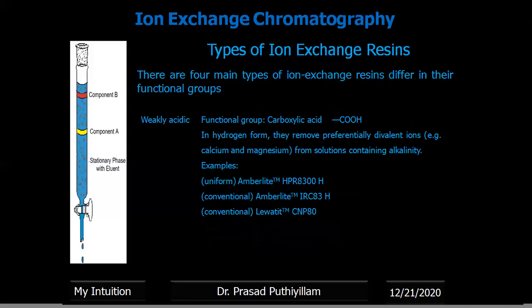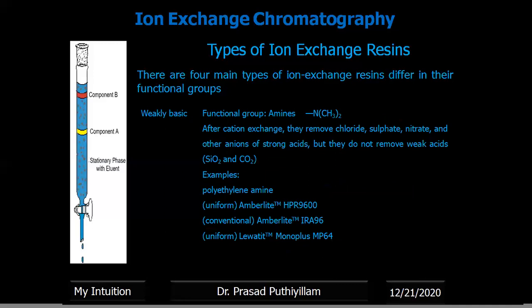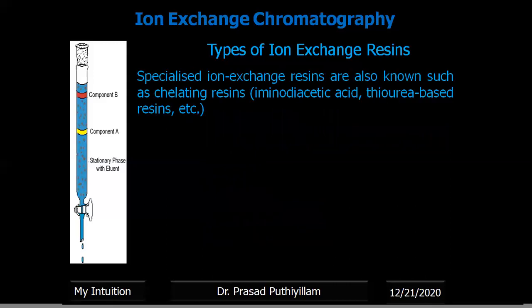Weakly acidic ion exchange resins contain a carboxylic acid functional group (–COOH) in hydrogen form. They preferentially remove divalent ions such as calcium and magnesium from solutions containing alkalinity, and can convert alkaline water to normal water. Weakly basic ion exchange resins contain amines — usually a secondary amine with a dimethylamine structure. After cation exchange, they remove chloride, sulfate, nitrate, and other anions of strong acids, but do not remove weak acids like SiO₂ and CO₂.